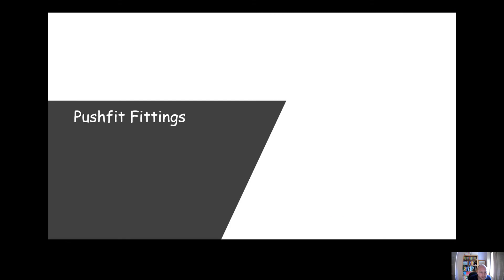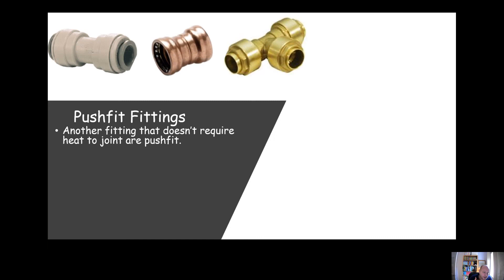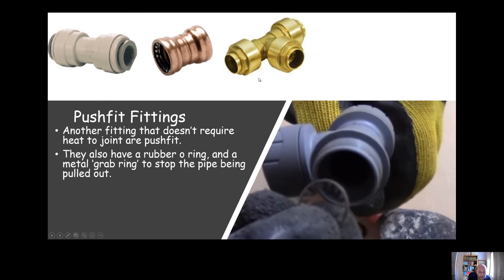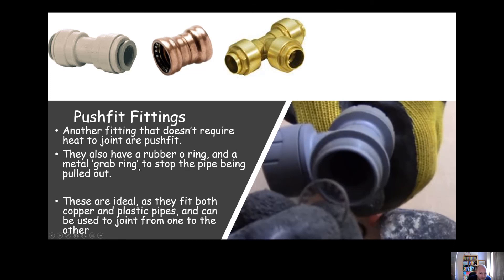Push fit fittings are another fitting that doesn't require heat to create the joint. You can see a few examples of push fit fittings. They can look very different, but in general they all work the same way. They've got a rubber o-ring inside them, they'd have a grab ring like you can see on this middle one up here with the teeth pointing backwards. That way, once you've pushed the pipe in, those teeth essentially stop the pipe from being pulled out, and the rubber o-ring will help keep it watertight. There's various ways of removing them depending on the material. You can see the grab ring just here in this picture as well. Easy to fit, fairly easy to remove generally speaking.